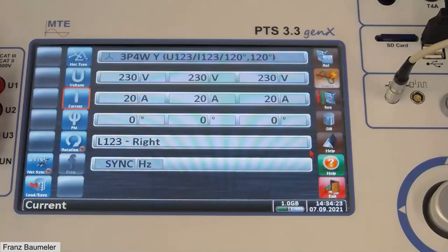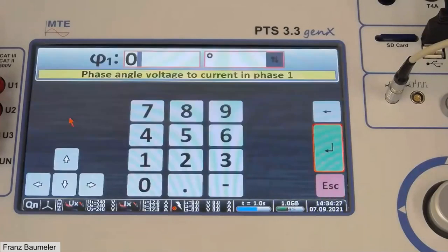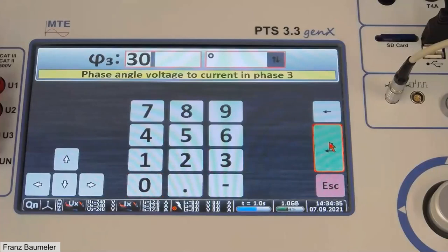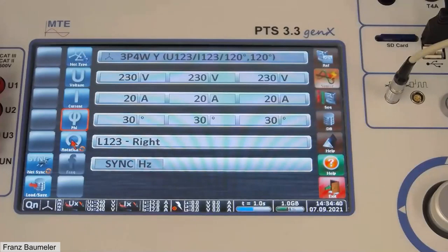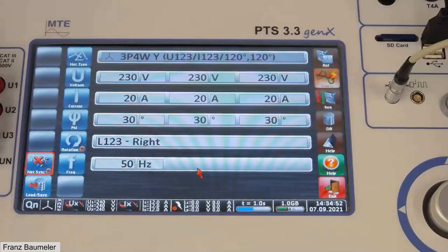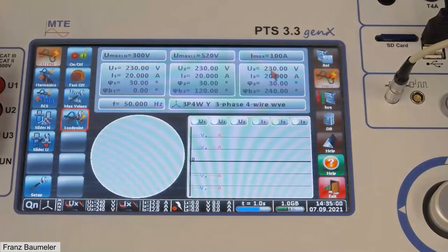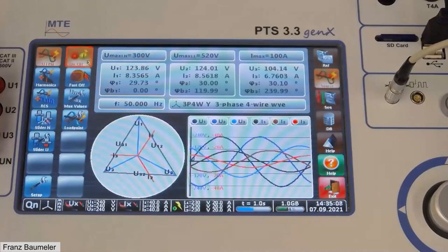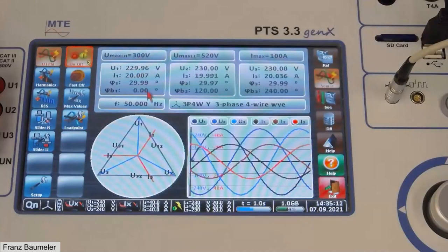I repeat the enter key to copy the current to phases two and three. Then I can define the phase angle between current and voltage — for example 30 degrees for phases one, two, three. Here I can change the phase rotation: right or left — we leave it at right. Then I program a frequency of 50 Hz; typical values are 50 or 60 Hz, or synchronized to line frequency. Now the values are prepared. I press the ON button and the values are switched on. We can see the measured values, the vector diagram and waveform — a nice overview.